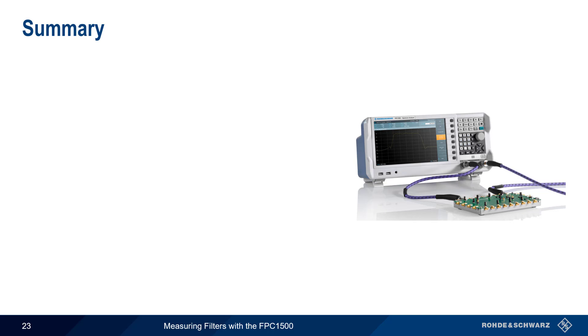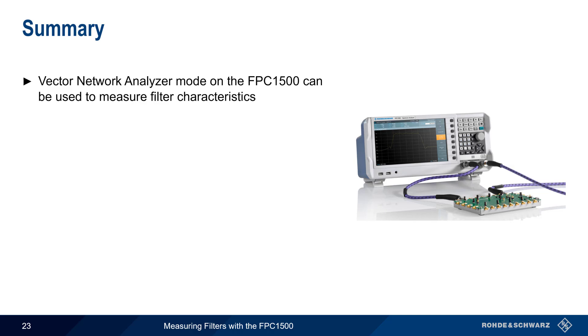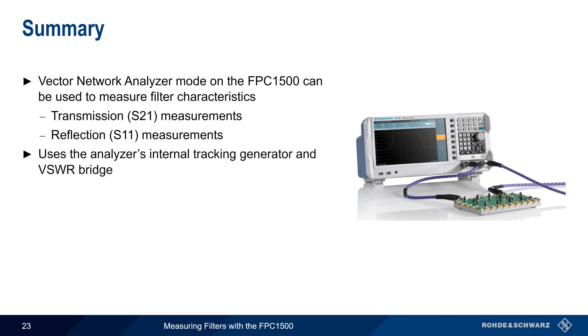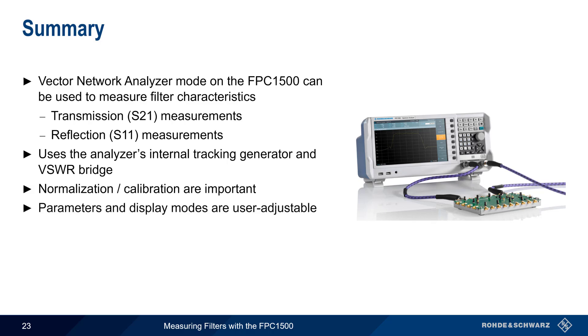Let's end with a brief summary. Vector Network Analyzer mode on the Rohde & Schwarz FPC-1500 spectrum analyzer can be used to measure filter characteristics, including both transmission or S21 measurements, as well as reflection or S11 measurements. These are made by using the analyzer's internal tracking generator and VSWR bridge, so no additional external devices are needed. However, it's important to perform a normalization or calibration before making measurements, and these require either manually attached calibration standards or an automatic calibration unit. Measurement parameters and display modes are user adjustable, and filter characteristics such as frequency, bandwidth, attenuation, and ripple can all be easily measured using markers.